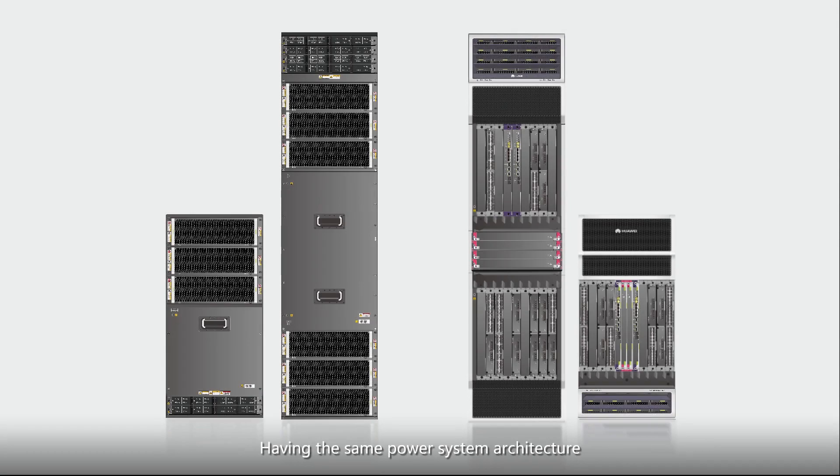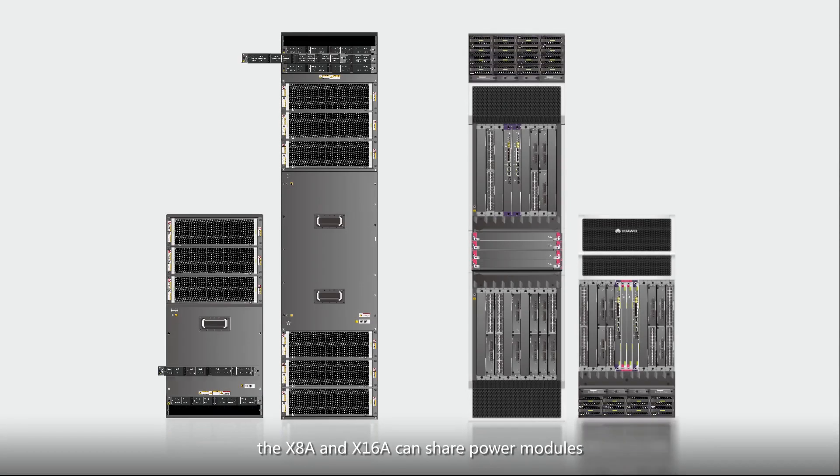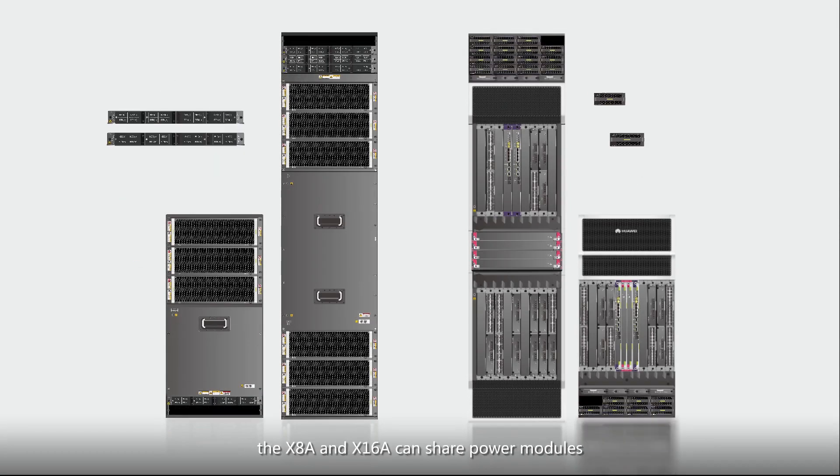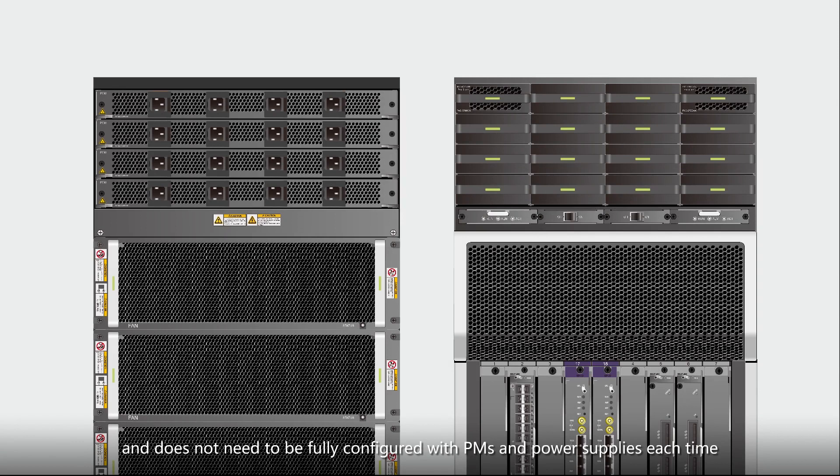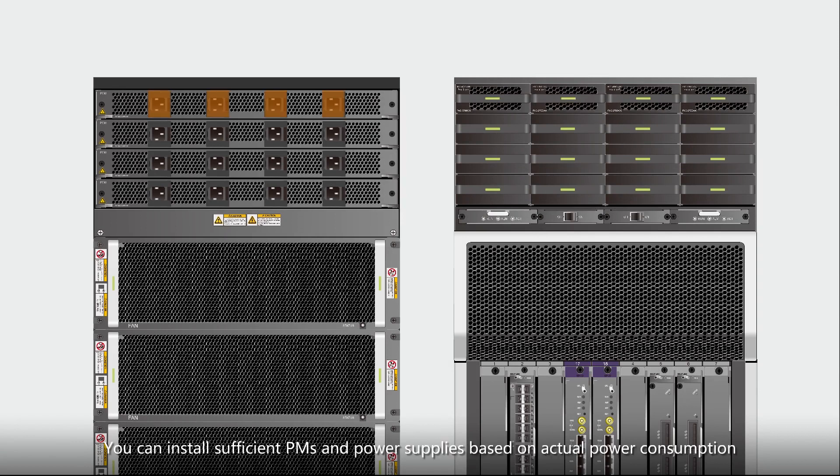Having the same power system architecture, the X8A and X16A can share power modules. The system uses a non-partitioned power supply and does not need to be fully configured with PMs and power supplies each time. You can install sufficient PMs and power supplies based on actual power consumption.